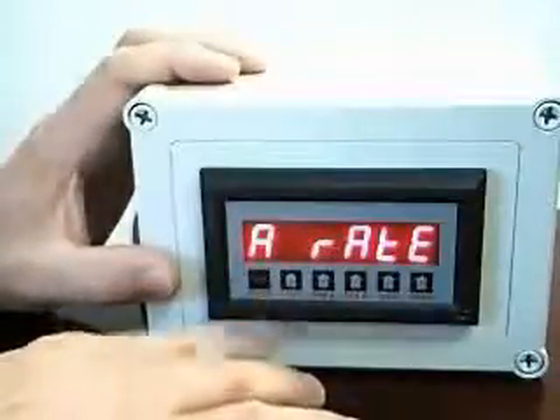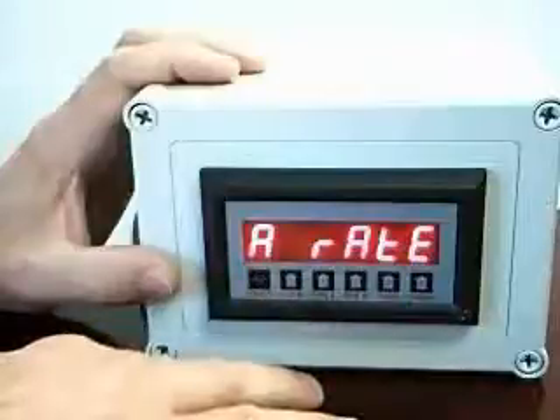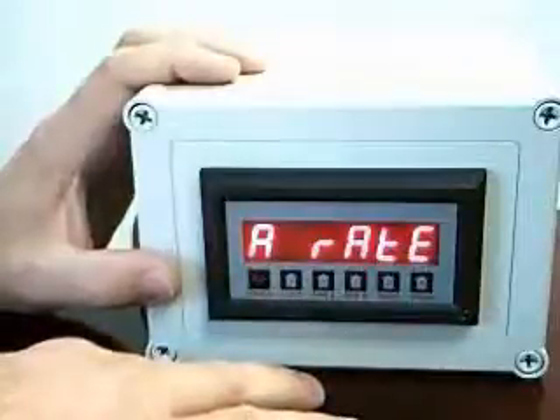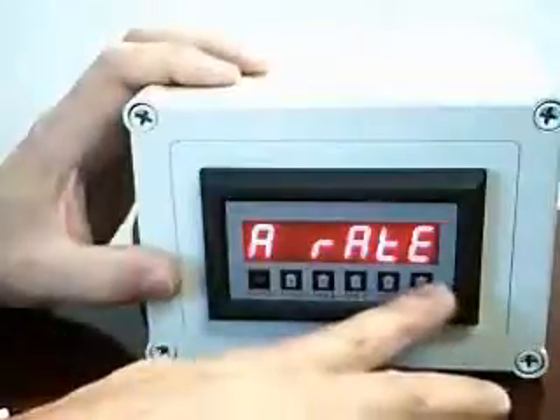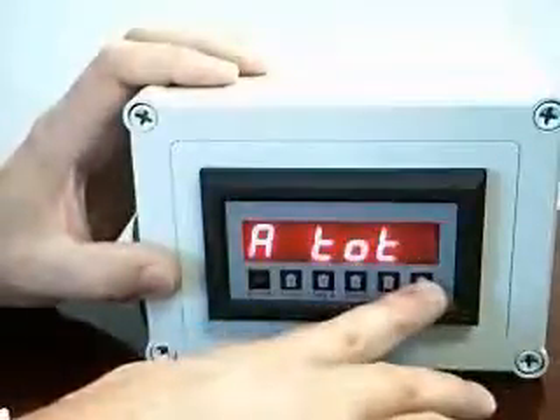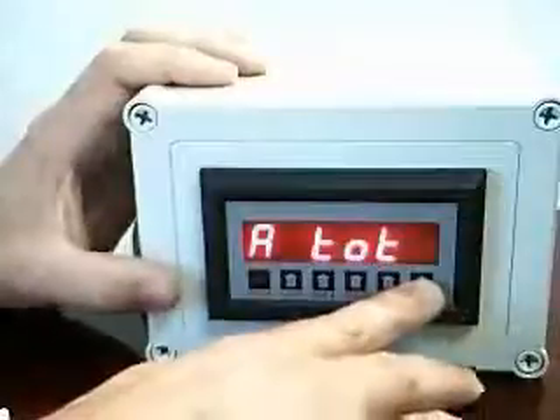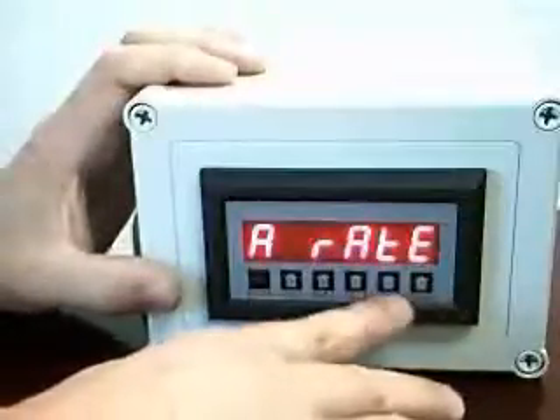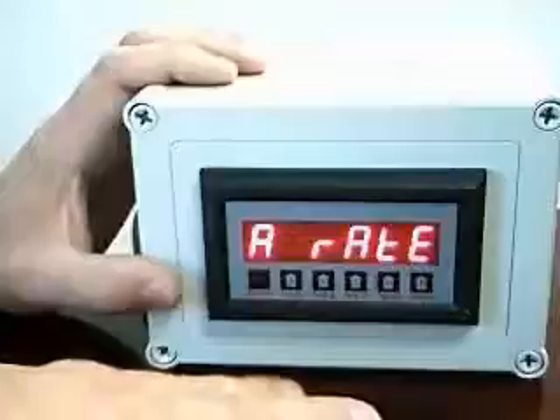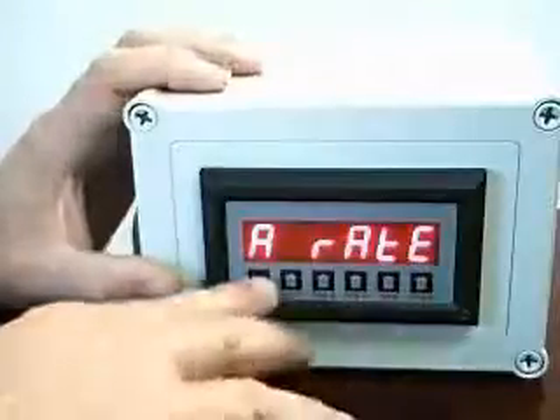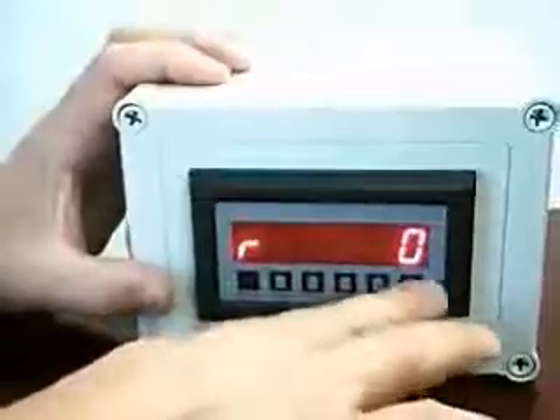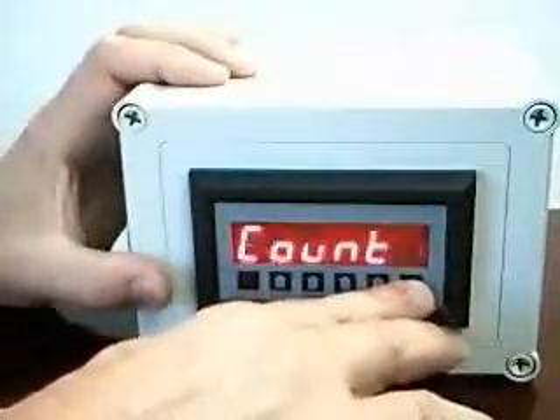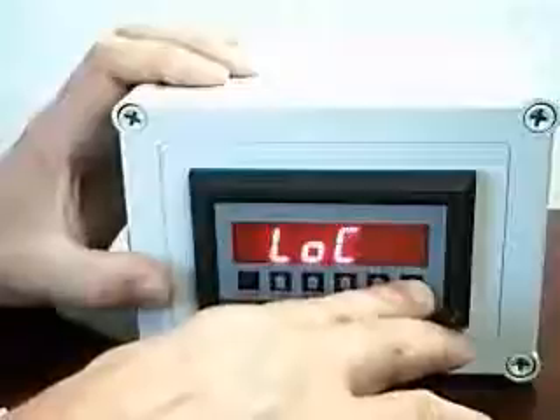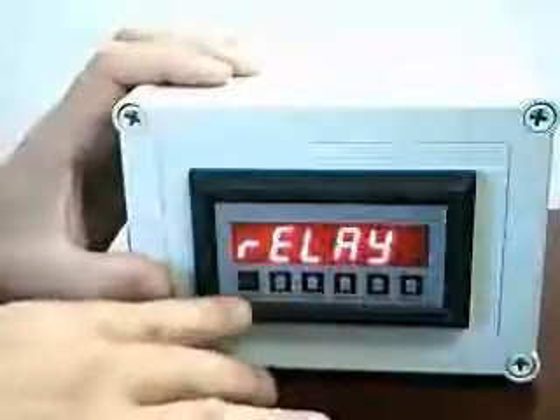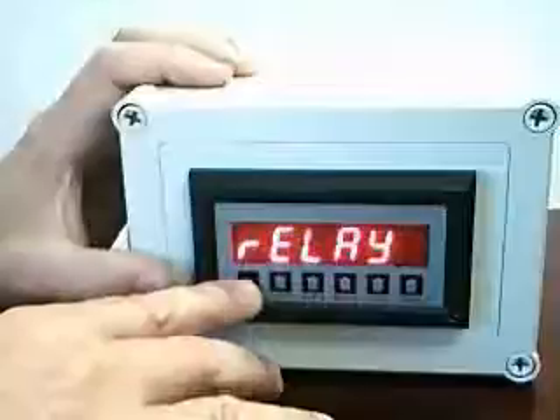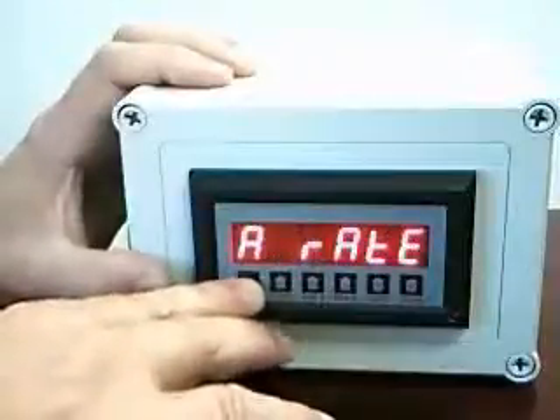The first relay, indicated by the A, is currently assigned to rate. There are other modes of operation, and these are to assign it to total. In our application, we want to use it as a rate alarm, so we're going to leave this assigned to rate. Unfortunately, I had pressed the button too quickly and moved out of that menu group prematurely. I'm just going to go back into that mode so I can show you the B relay.